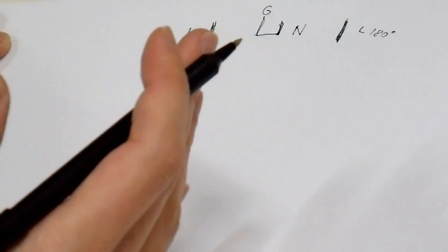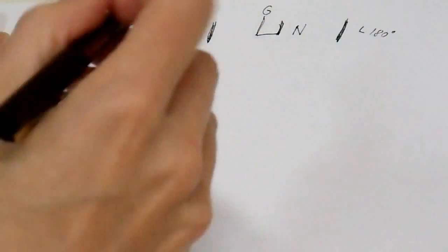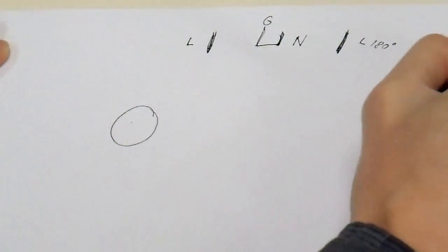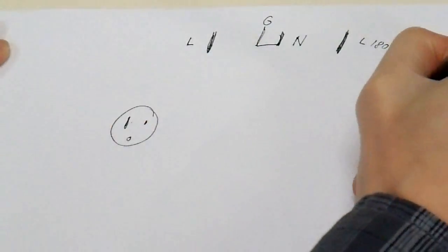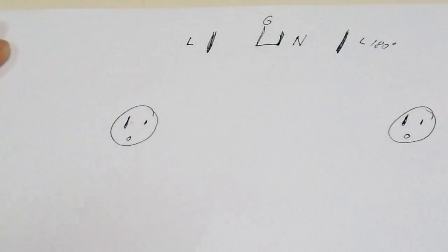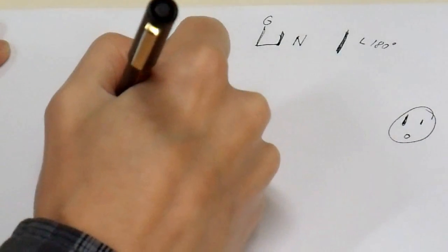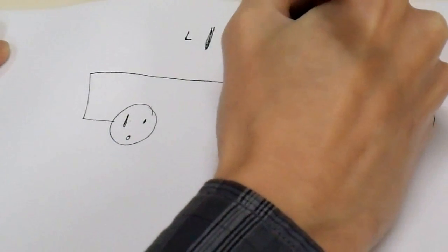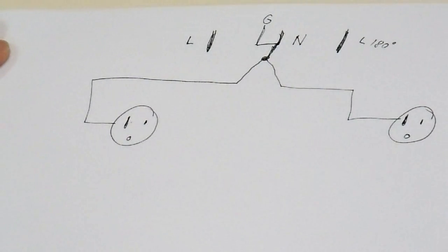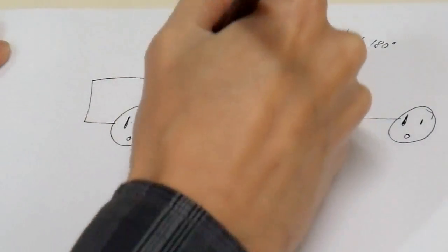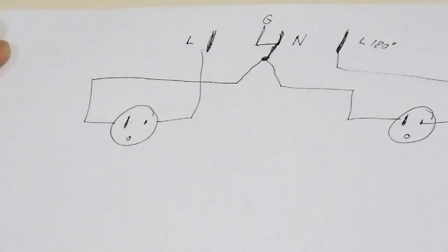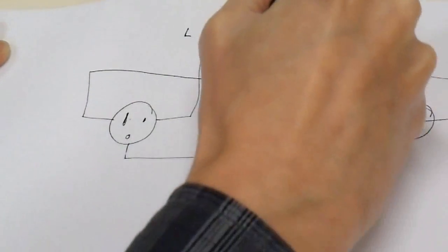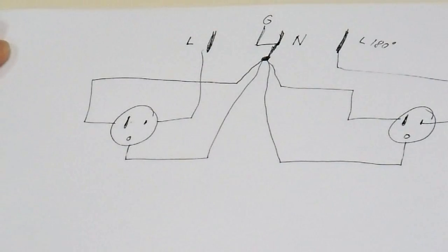Now I have two different circuits in my garage, and I plan to use those to power my whole house, both phases. This line and line 180 degrees. So those outlets are, I'll just draw them this way. Excuse the crudeness of my drawings. But they have one large prong, one small prong, and a ground. Now the large prong over here, that is neutral. So these are just going to go out here and tie up to neutral. And they're just connected like that, connected directly together. Now the hots, one of these goes to this line and this one goes to this line. And ground, well ground actually goes directly to this same node. Ground and neutral tied directly together.